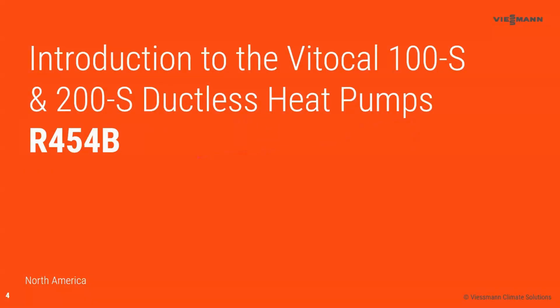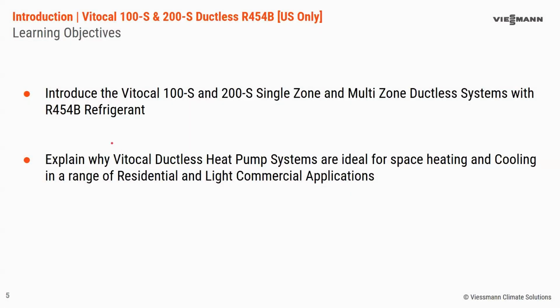We're here to talk today. We're going to start about the Vitocal 100S and 200S ductless heat pumps. These are air-to-air heat pumps using R454B refrigerant. So what we're going to be talking about in this presentation are the 100S and 200S single zone and multi-zone ductless systems. So to be clear, everything in this presentation is ductless air-to-air heat pumps using the R454B refrigerant. And we're going to talk about why the Vitocal ductless heat pump systems are ideal for air-to-air space heating and cooling in applications from residential up to even light commercial.